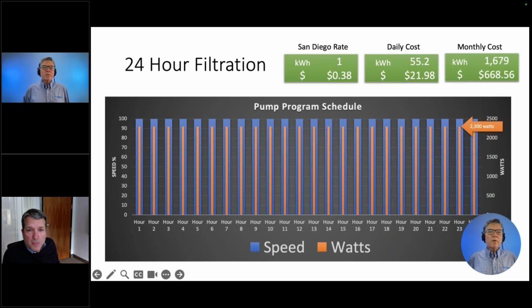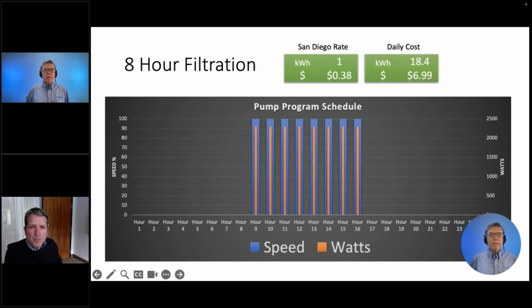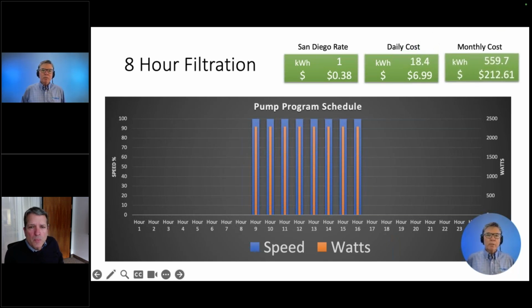So what do we do? We install a variable speed pump and run it on high speed for 1 turnover, 8 hours a day. So we reduced the cost by a third, same rate. Our kilowatt hours have dropped by 2/3, and that means our energy bill has dropped by 2/3 also. So instead of $22 a day, we're looking at $212 a month. For California, this is an unfortunate reality. So let's stick with this.